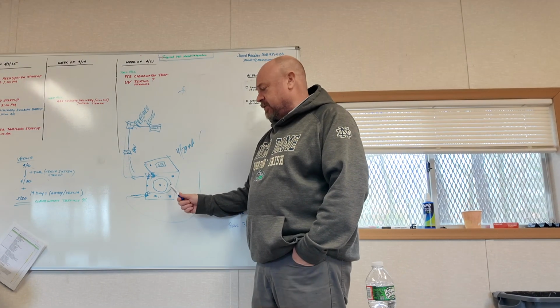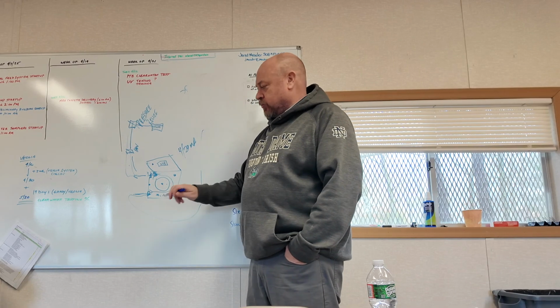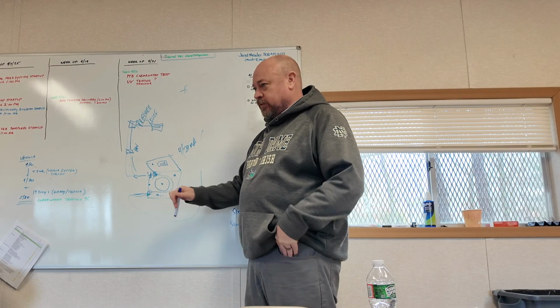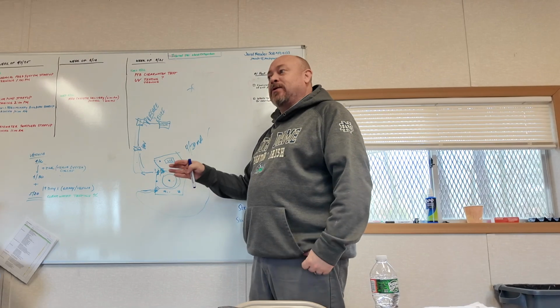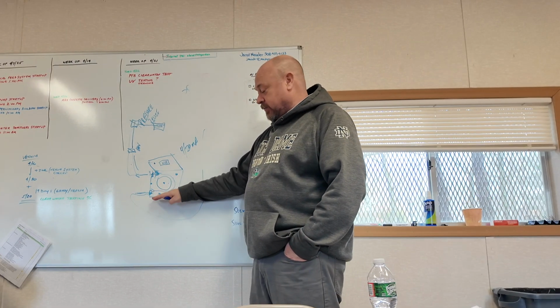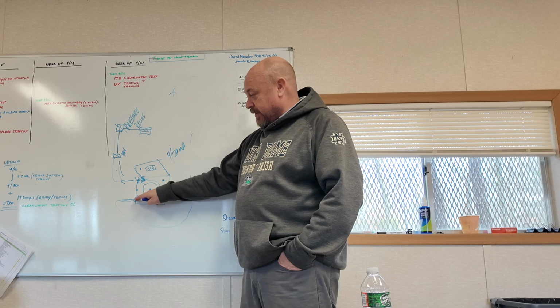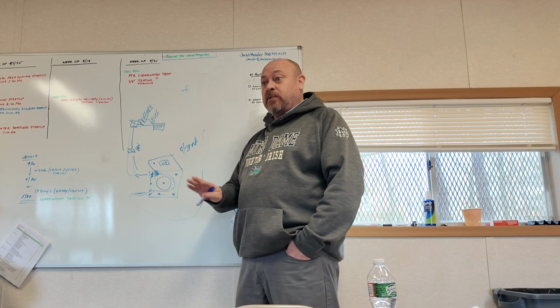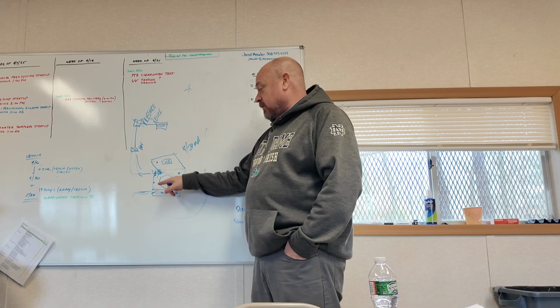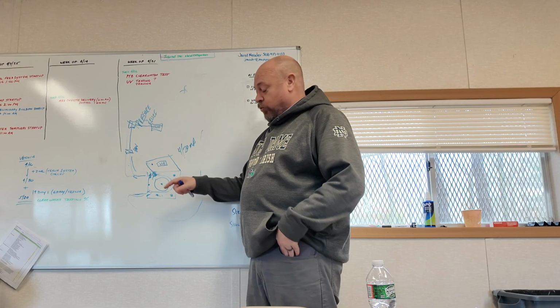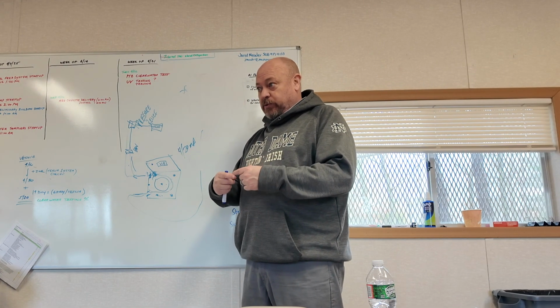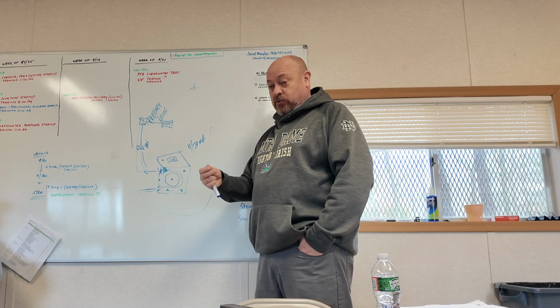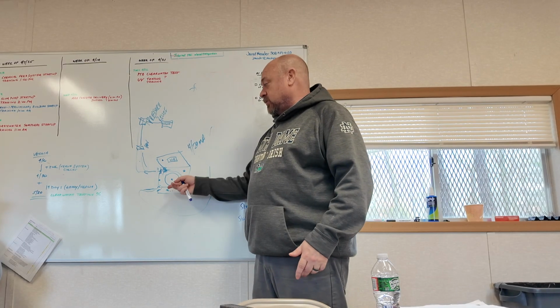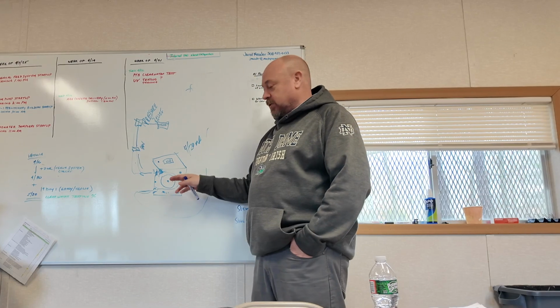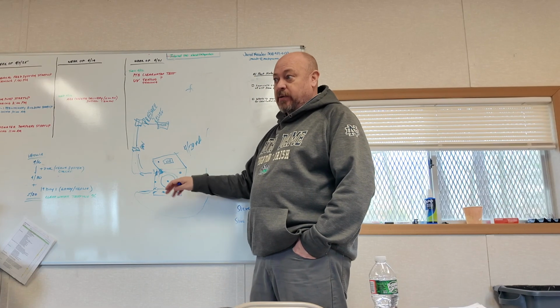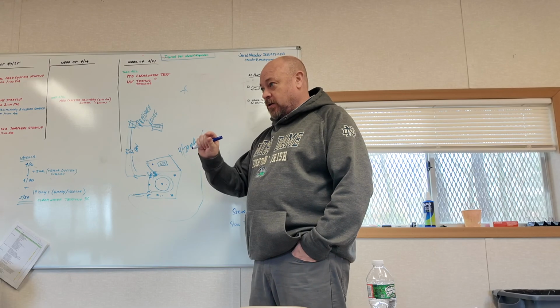If you do have a chemical leak, depending on the severity of the leak. So when we go out there, I'll show you where this cover sits over these tube fittings. There is a little bit of a gap. So as product, say it's on a weekend or a holiday break and product's allowed to continue to fill the pump, it'll only get to about this bottom portion before it starts to weep out. For whatever reason, the pump doesn't shut off, or you try to override the alarm and you get chemical up into the roller assembly. The roller itself has stainless pins that keep the roller in place. So if you get sodium hydroxide or hypo crystals inside there, you could bind those. So if you do have a leak, take this out, run it under hot water, make sure there's no chemical in the roller assembly, and then put the roller assembly back in. On the shaft, there is a guide, a wear washer.